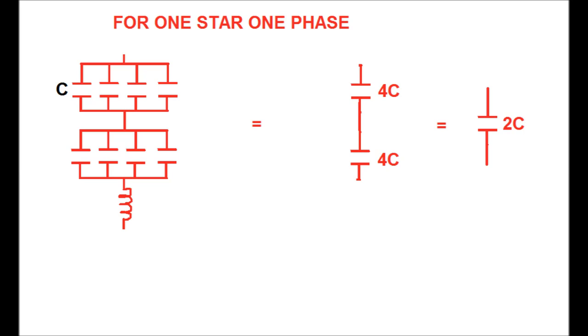The equivalent combination for four units in a parallel group gives 4C. This 4C capacitance is then connected in series with another 4C. When two capacitors of equal value are connected in series, the equivalent value is half. Therefore the equivalent capacitance for each star in one phase comes to 2C.